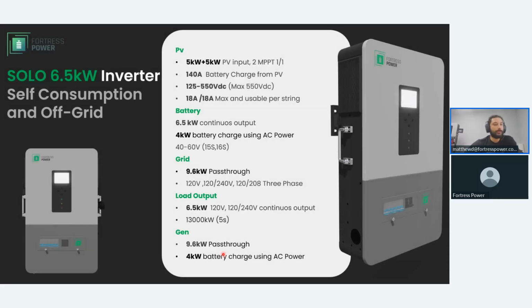All right. So off the bat, the first thing I want to introduce about this inverter is that it's a 6.5 true output inverter, and not just when it's at 120/240 split phase configuration, but also at a 120 single phase configuration. Let me say that again. It is also a 6.5 kilowatt inverter at a 120 volt single phase configuration. That means from line to neutral. Now we're going to go over some of the installation processes on how to achieve that, because there is a special installation connection process to achieve that. But nonetheless, it can do that, right?